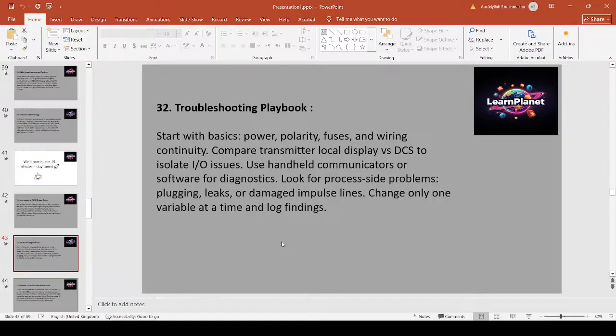Start with basics: power, polarity, fuses, and wiring continuity. Compare transmitter local display vs DCS to isolate I/O issues. Use handheld communicators or software for diagnostics. Look for process side problems, plugging, leaks, or damaged impulse lines. Change only one variable at a time and log findings.